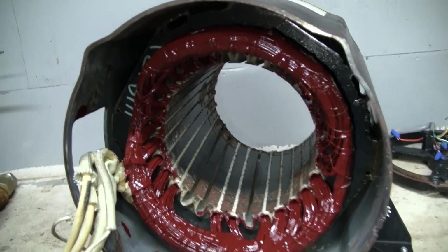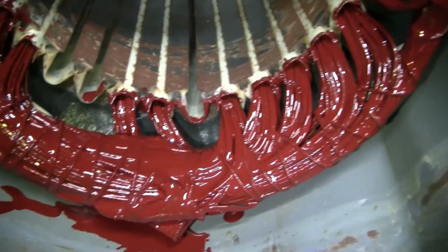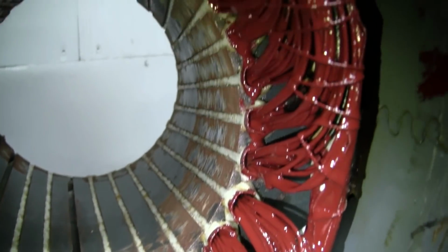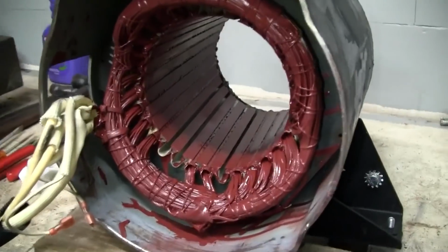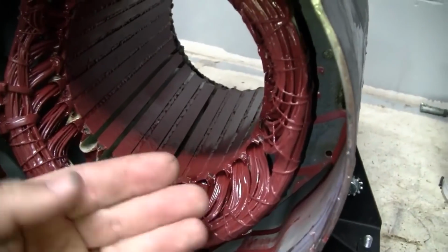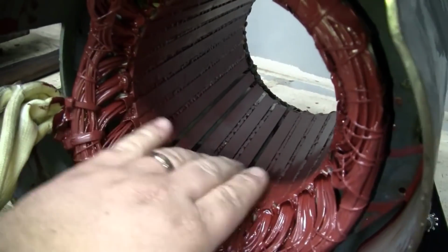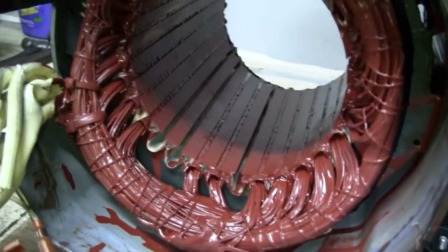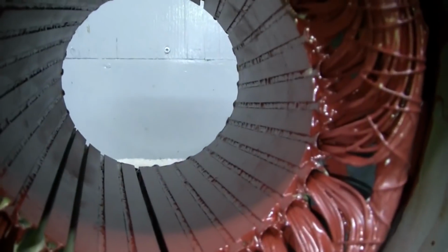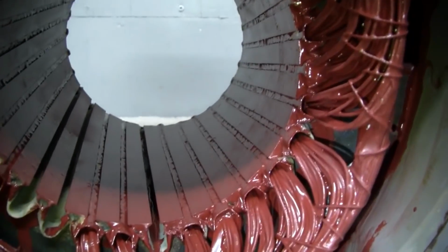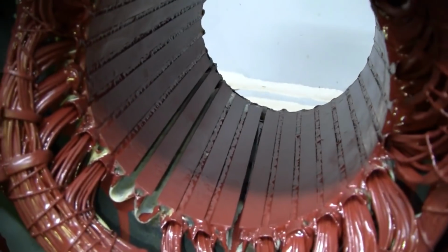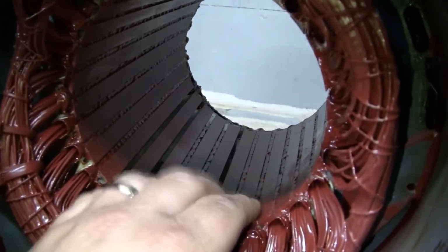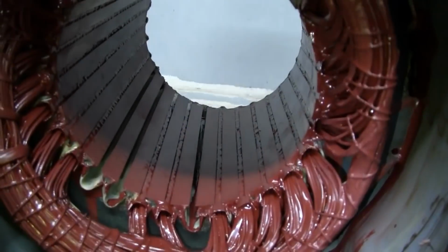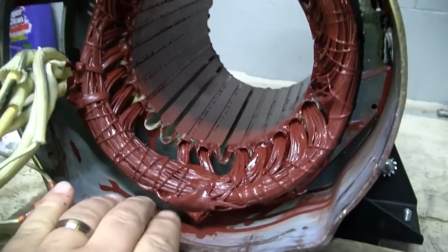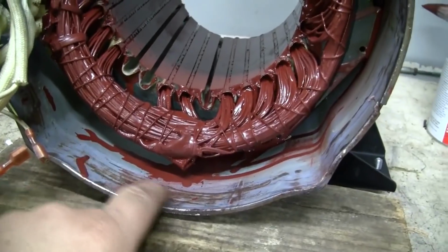Okay, well there's the first coat. Just letting it soak in. So the stator's done. It's got 2 coats of the Glyptal on there. It's not quite dry. It's still a little bit tacky. I think it came out pretty nice. I coated the inner laminations here as well, just to prevent any rust from forming. It's a really thin coating, so it's not going to interfere with the rotor at all. So I've made a little mess here. I should be able to wipe that up with some lacquer thinner.